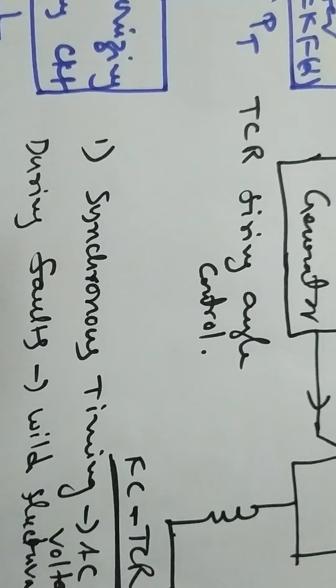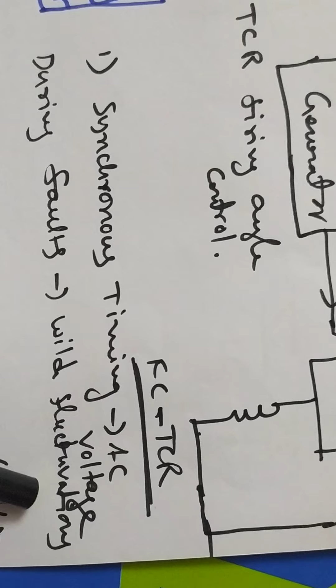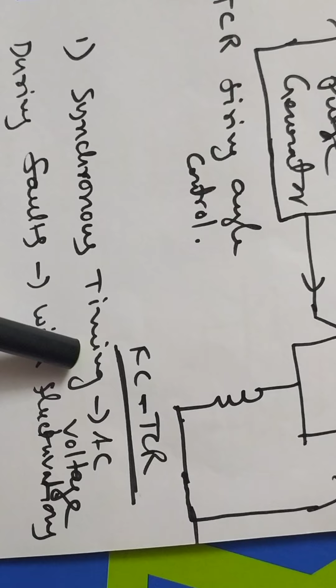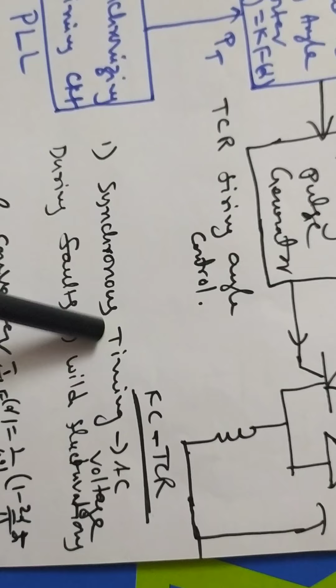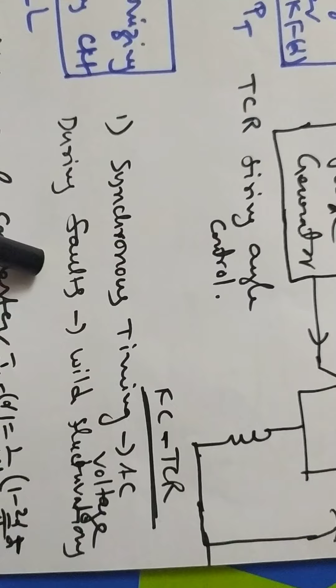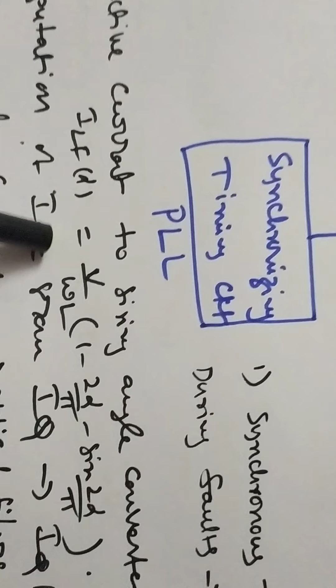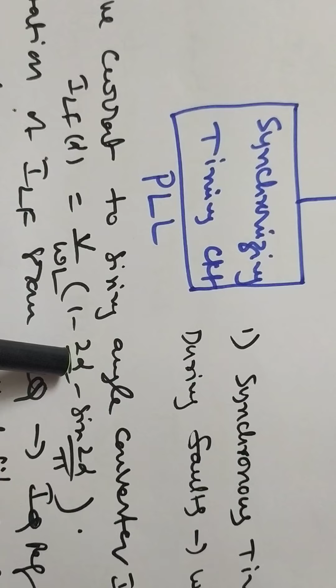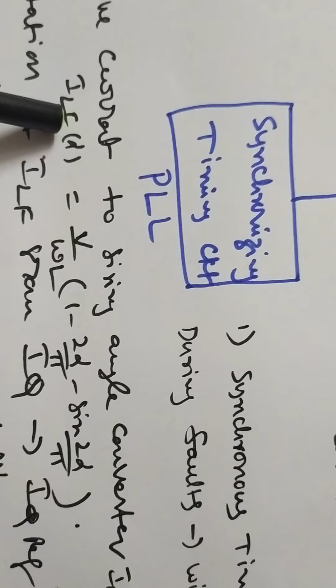If you summarize all the functions of your FC-TCR type SVC, the very first one is synchronizing and timing signals during fault conditions. While fluctuations occur in the voltage, the AC voltage is measured here and given to the PLL circuit, which generates the synchronizing signals for the control circuit. That is the first function. The second function is the reactive current to firing angle converter. ILF alpha is known, alpha is unknown. From this equation, you can obtain the alpha value from lookup tables or a computer program. So this is the second function.